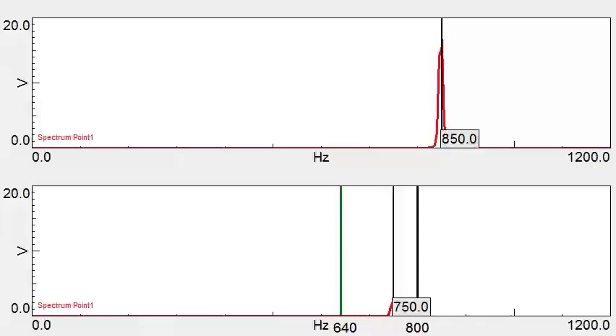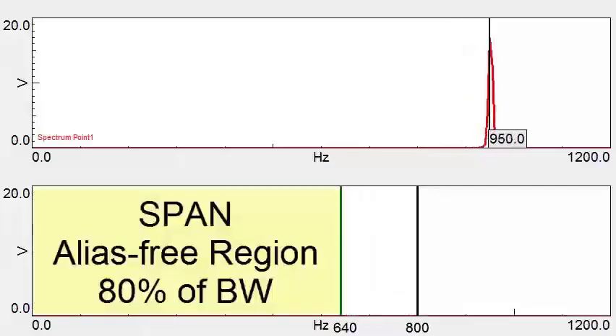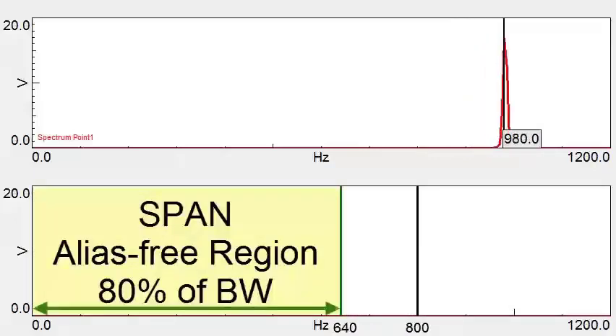The anti-aliasing filter will completely attenuate incoming signals that are 20% above the specified bandwidth, therefore leaving 80% of the bandwidth alias-free. This alias-free region is called the span. Thank you for watching!